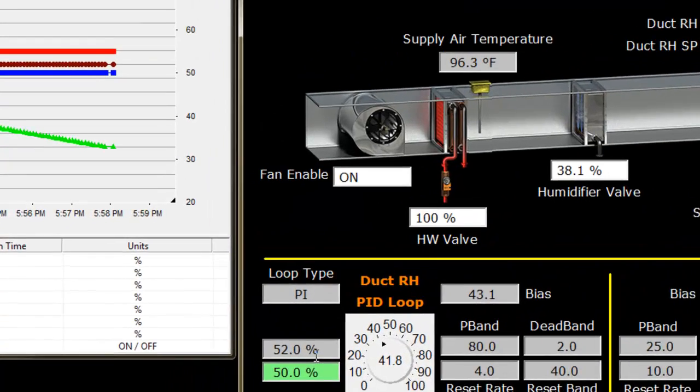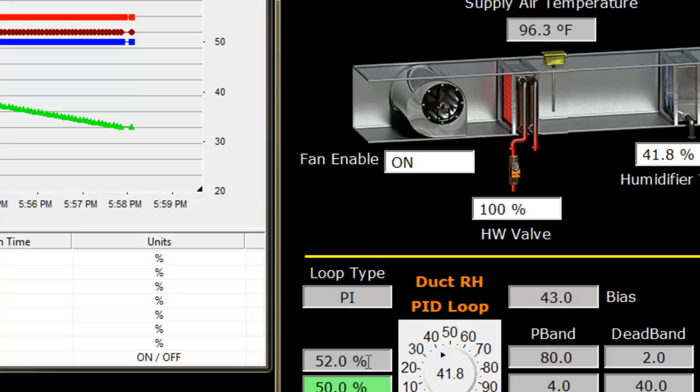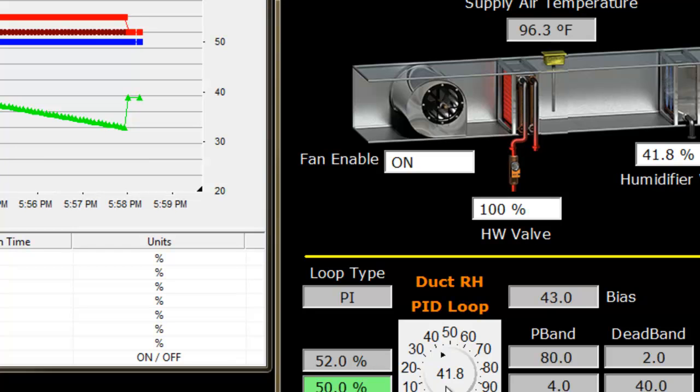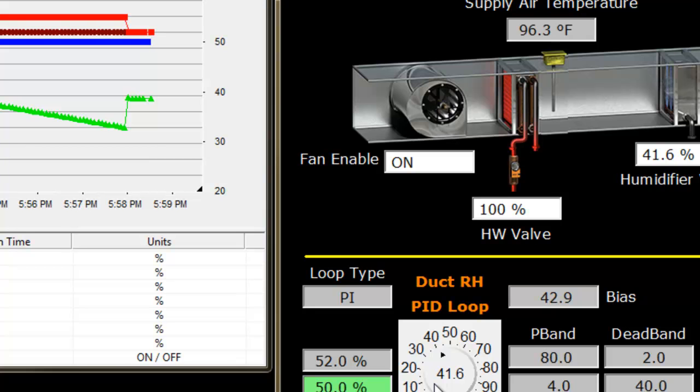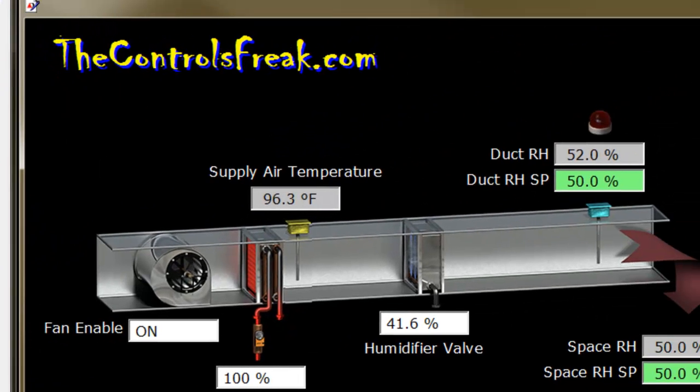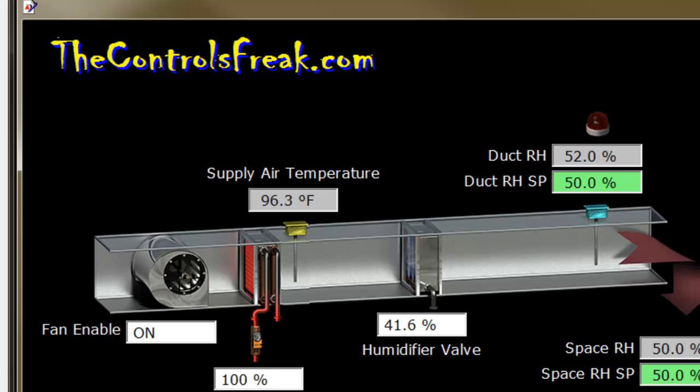The graph is slightly delayed, but you'll see that jump with the green line—that is our valve reacting to the RH loop. Now the PID loop is at 41. The whole effect of the integral controller is that it continues to adjust at a very smooth rate. With proportional-only you get a back-and-forth motion.